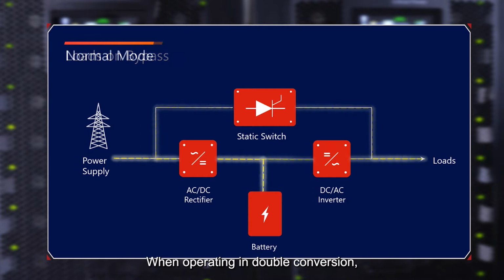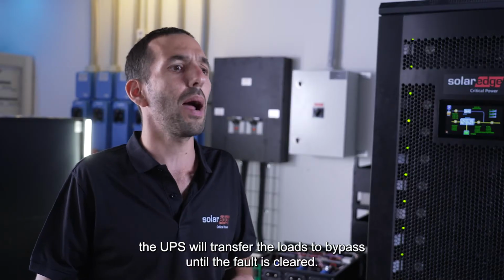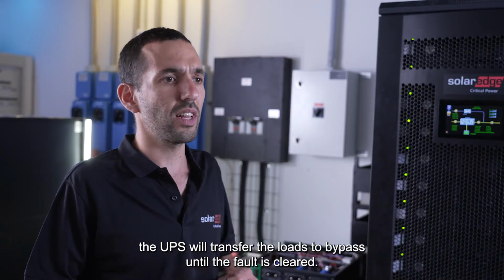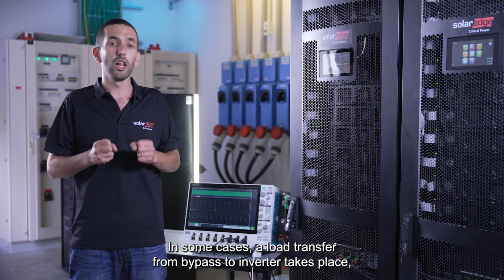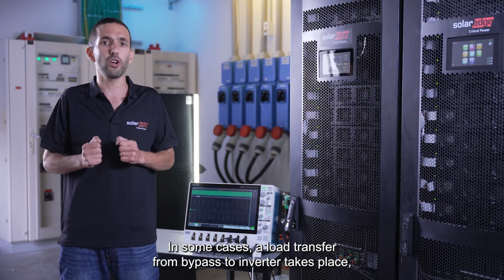When operating in double conversion, in case the inverters cannot support the load, the UPS will transfer the loads to bypass until the fault is cleared. In some cases, a load transfer from bypass to inverter takes place.